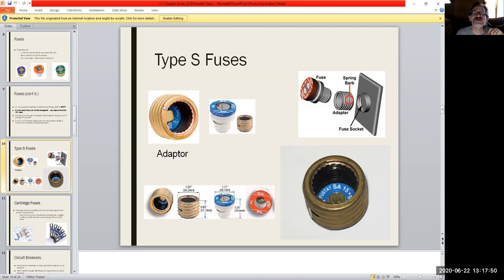So what they would do is they would have these adapters. You could screw it in, and then instead of a 15, now you could have a 20 amp. Now remember, you haven't changed your wiring size. Who's the most dangerous one out there, right? Homeowners and renters, because you have just enough knowledge to go, oh yeah, we could change that up. But by not changing your wiring size, if you kept running this thing, your wiring is going to end up getting hot.